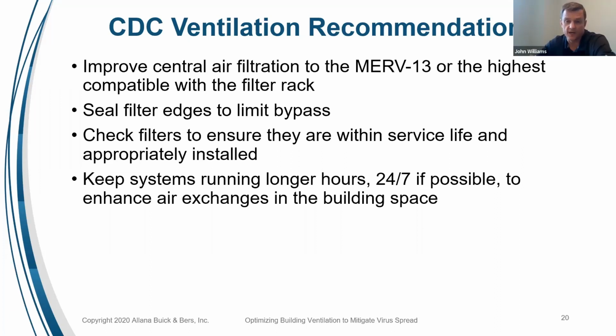So we want to basically find that balance between the higher efficiency filter and the amount of airflow we can move in our building. We also want to seal up the filter edges. Often the filters in these filter racks have degraded over time, and the filters do not fit tightly and snugly in there. And portions of the air are going to bypass the filter. Along with this point, you really want to also make sure the right size filters are installed. And simple as that sounds, many times I've opened up HVAC units and found makeshift filters or filters that are the wrong size installed, which allow air to bypass the filters.